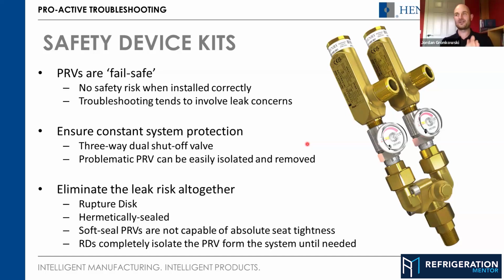So there are a number of things a PRV has to achieve, pressure tolerance wise. There is a leak tightness test. Starting at the bottom end, the standards leave it open to the manufacturer to determine how they do a leak tightness test and what pressures are involved. But they always recommend the API 527 standard, which is a seat tightness standard. The leak tightness test that we do at Henry is at 90% of the set pressure. Up to 90% of the set pressure, there should be no leak on the API 527 method, which is basically the outlet of the valve gets connected to a tube, which goes into a beaker of water, usually. And then you look for bubbles at the outside of the tube. So at 90%, you should have no bubbles from the tube.